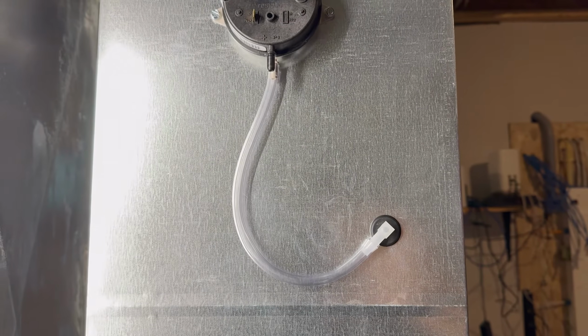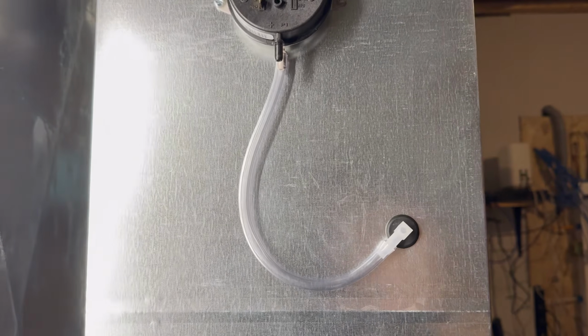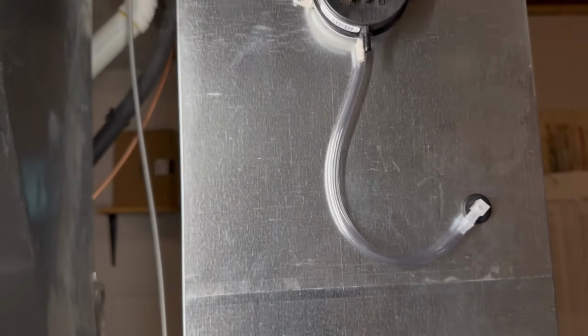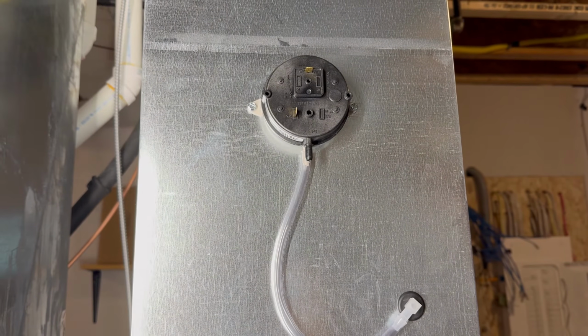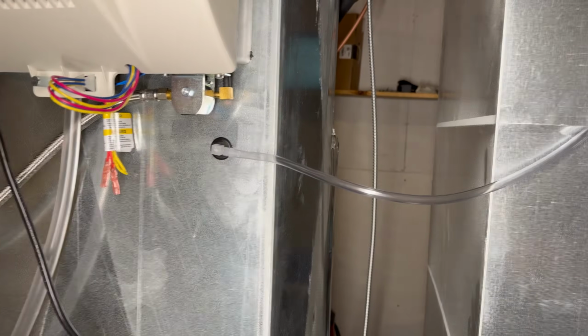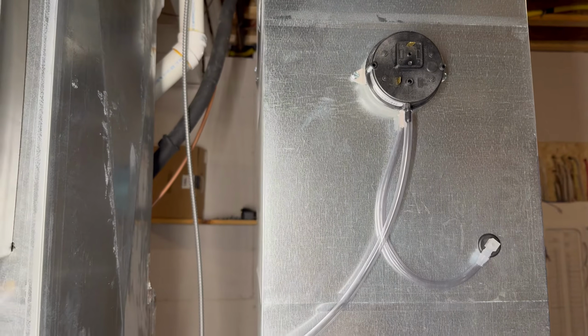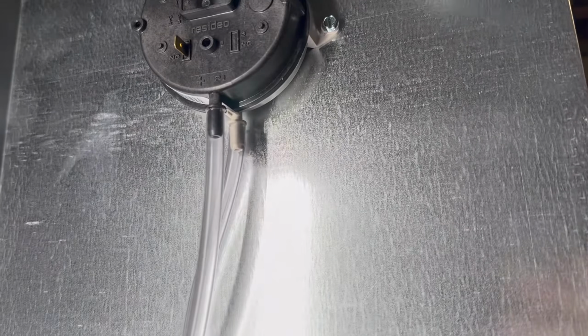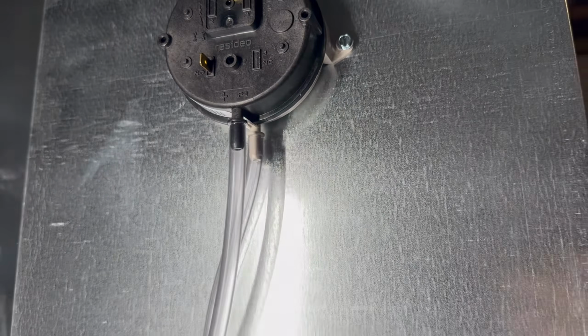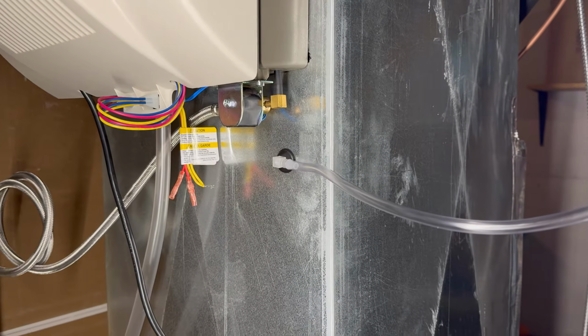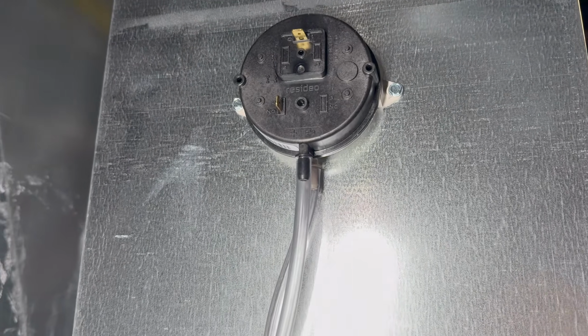Now you'll cut a piece of vinyl tubing and connect the return side to the gray port on the pressure switch. That's the one in the back. And then you'll cut another piece of vinyl tubing to go from the supply side to the front of the pressure switch, which is the black port. There you have it. Return side and supply side, both connected to the pressure switch. Again, remember, the vinyl tubing from the return side goes to the gray port on the pressure switch. That's the one in the back. And then the vinyl tubing from the supply side goes to the front, which is the black port.